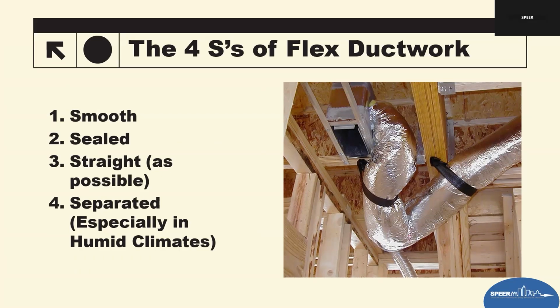So the four big S's that we need to see from flex duct out in the field are smooth, sealed, straight as possible, and then separated, especially in warm, humid climates. They should not be in contact with framing members. They should not be in contact with each other. They should be separated. I don't care if it's just a quarter of an inch or a half inch.